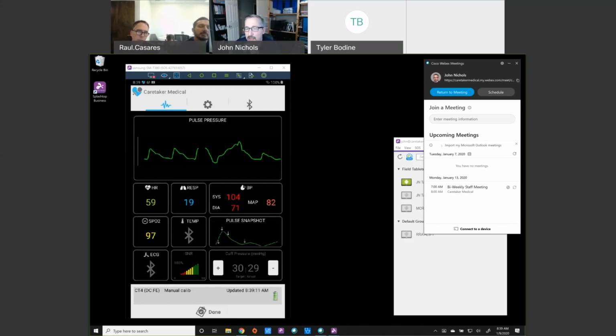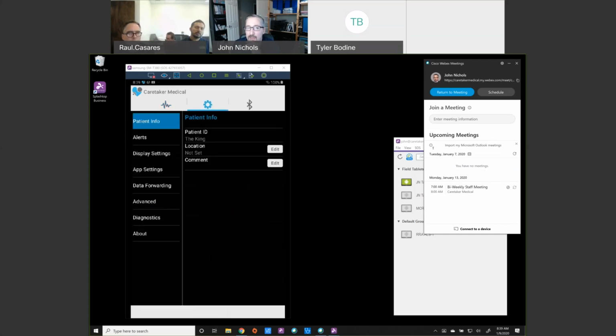Okay, so ultimately, the only time that you ever need to adjust the cuff is if a patient might complain it's too much pressure. But just keep in mind that you want to watch the signal to noise bar chart. If you lower the pressure on the cuff, you still want to make sure that you've got basically some green bars going on. Make sense? Okay. Other than that, we've kind of covered everything. Now, let's go in, hit the icon in the top center of the screen that looks like the gear. Okay, so in here, a couple of things that I want to show you.